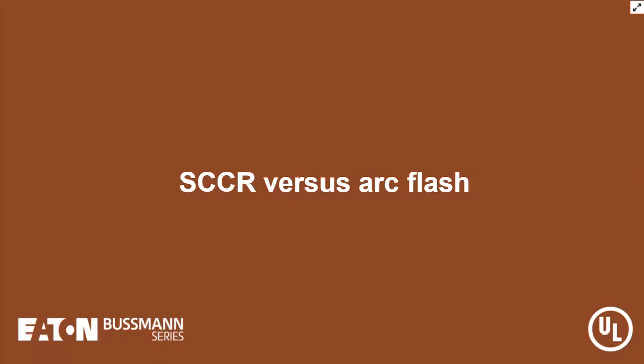Thanks, John. All right, so we basically talked about the machine SCCR, and the question that you have to ask is, do all of your machines and industrial control panels have an SCCR? And if they do, is it adequate for the available fault current? And if it is not adequate for the available fault current, do you have an arc flash label on there? And if you do, is there an electrical hazard? It's possible we have an electrical hazard because the SCCR is not adequate for the available fault current. And so we need to make sure that the SCCR is adequate for our arc flash label that we're going to be putting on our machines and our panels themselves.